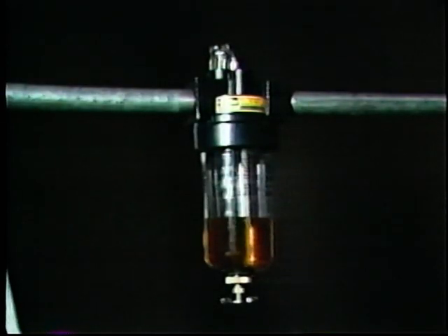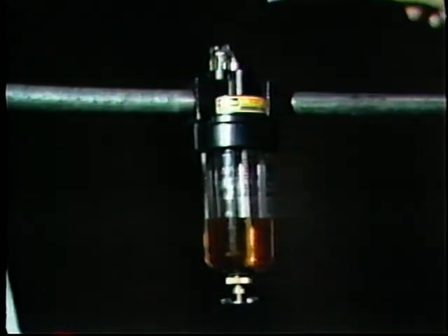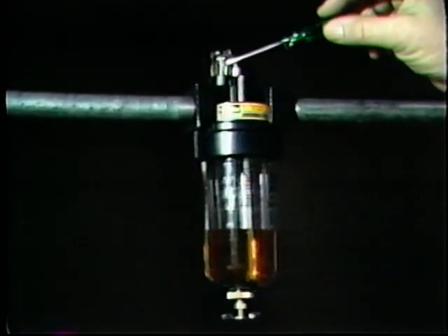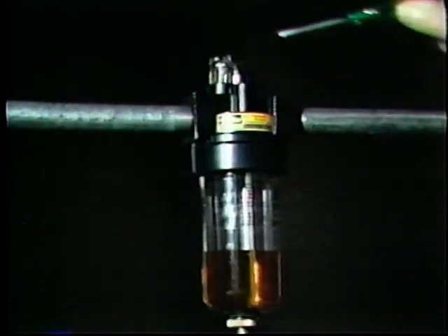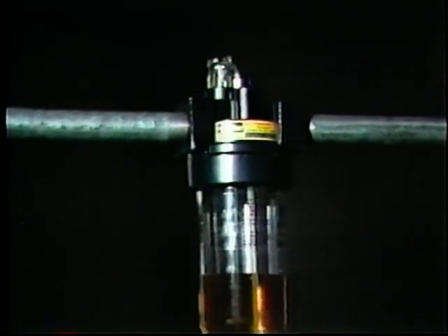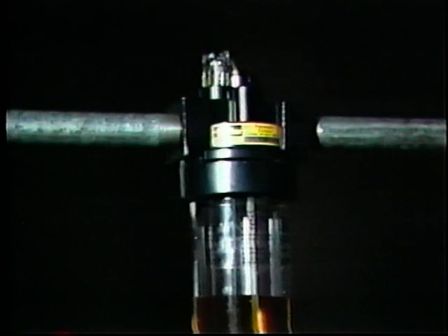A more popular method of lubricating is to spray the oil into the flowing airstream in such a way that it forms a mist. Most standard airline mist lubricators, like this one, can deliver oil particles ranging in size from 1/100th to 500 micrometers in diameter.